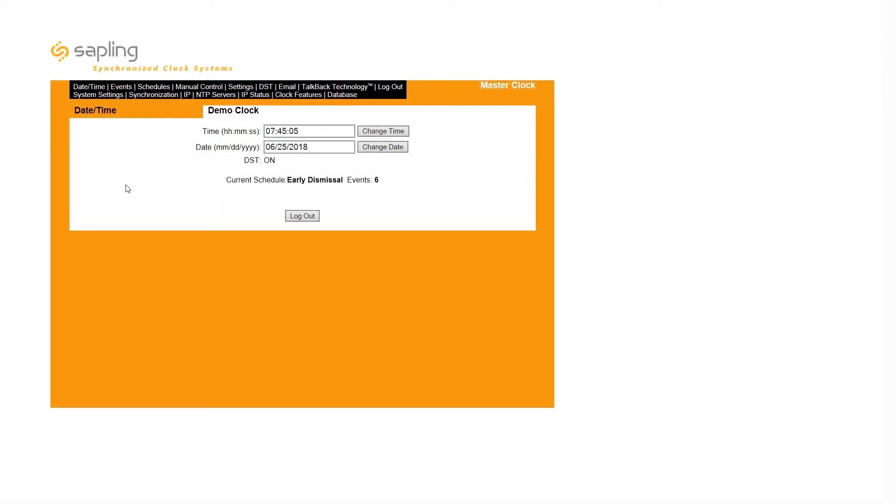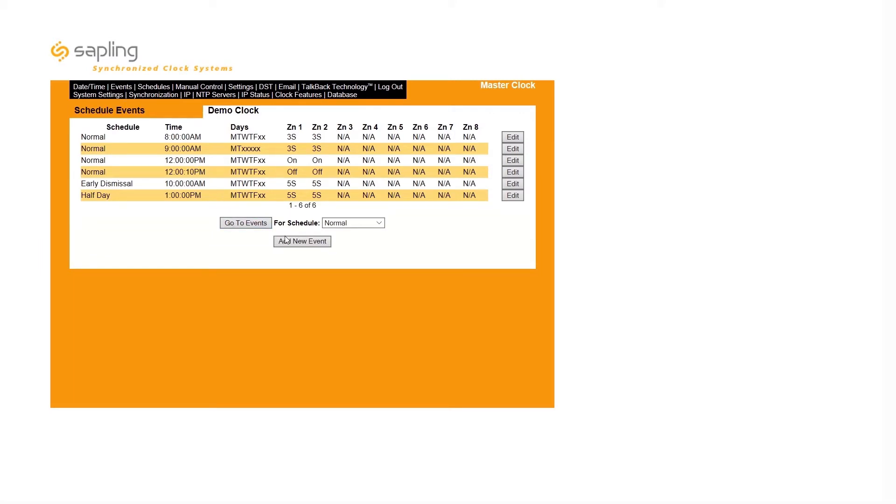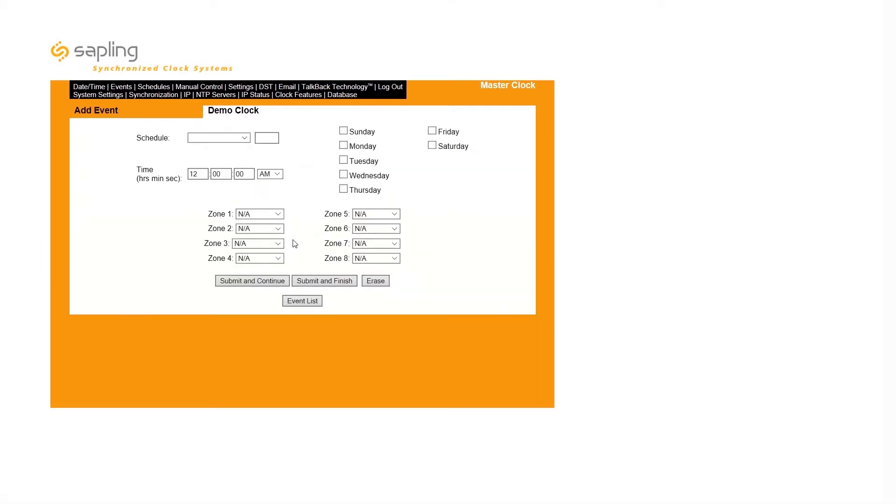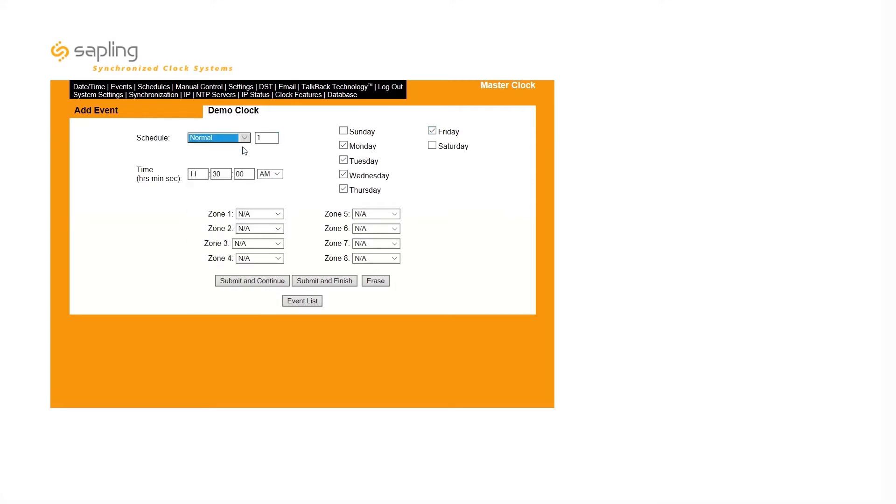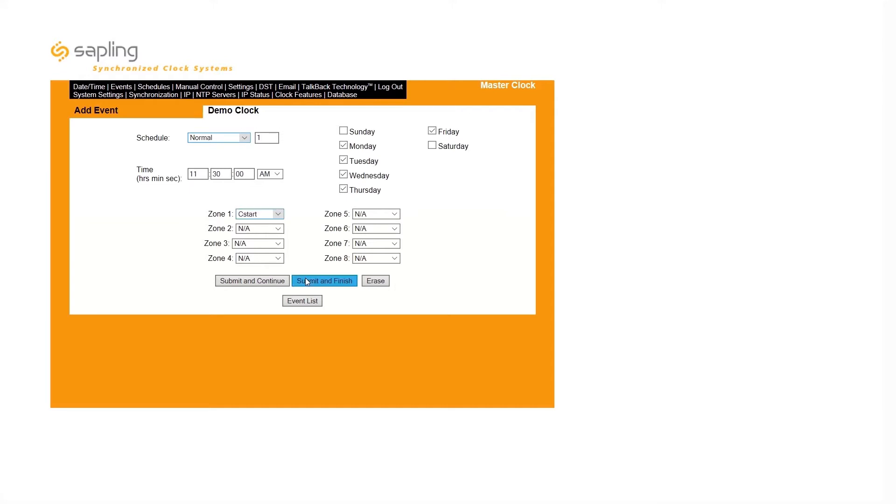Two unique events must be created for each countdown: a countdown start event and a countdown stop event. To add countdown events, select the Add New Events button to open the event configuration menu. First, input the time the countdown should begin, which days of the week the countdown should occur, and the schedule the countdown event should be assigned to. Then, select C-Start in Zone 1, and click Submit and Finish to save your countdown start event.